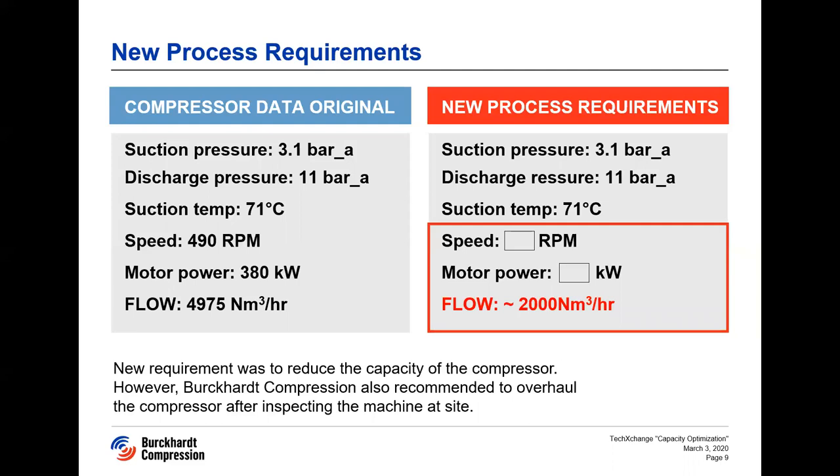To explain a bit about the client's needs: the client had new process requirements. Because of low production of gas, the flow expected on this machine was also low — almost less than 50% of the original flow. The client requested Burckhardt Compression to recalculate the compressor for the new operating parameters. The speed and motor power were left as variables to be calculated and checked for the new operating parameters, so an engineering study was needed with a lot of calculations.